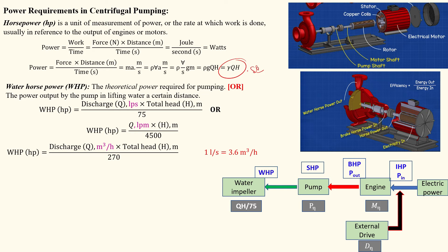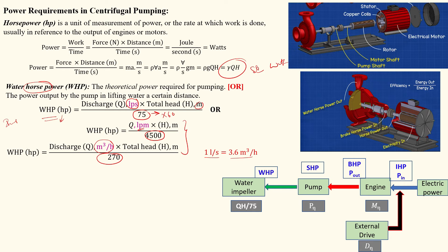Power can also be represented in imperial units as horsepower. The water horsepower formula is: discharge into total head divided by 75, where discharge is in liters per second and head is in meters. The value 75 is the conversion unit. Other forms include: dividing by 4500 for liters per minute, and dividing by 270 for cubic meters per hour. These are all forms of water horsepower.